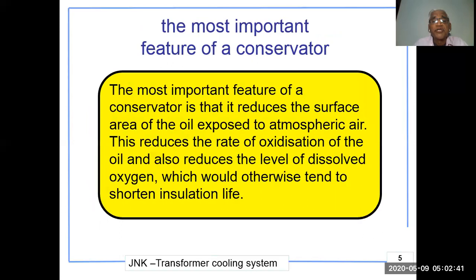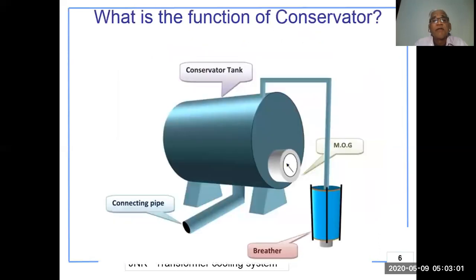The most important feature of a conservator is that it reduces the surface area of the oil exposed to atmospheric air. This reduces the rate of oxidation of the oil and also reduces the level of dissolved oxygen, which would otherwise tend to shorten the insulation life of the transformer.